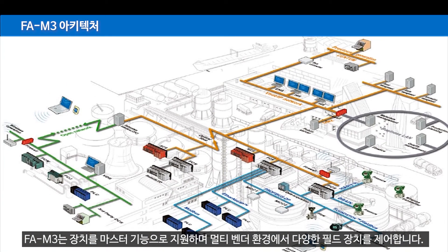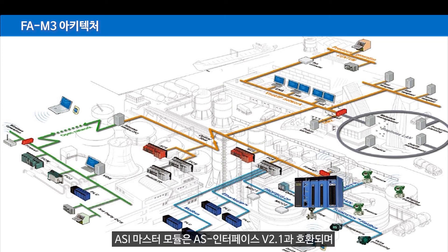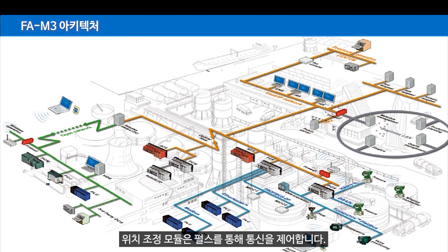FAM3 supports the DeviceNet master function and controls a wide variety of field devices in a multi-vendor environment, from sensors and actuators to sophisticated devices. The ASI Master module is compliant with AS interface V2.1 and is capable of controlling up to 62 ASI slaves. The Profibus DP interface module can communicate with up to 121 slaves. The positioning module supports mechatronic communications for independent axis movement.